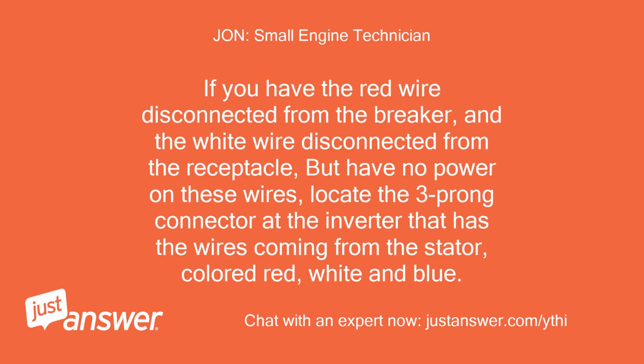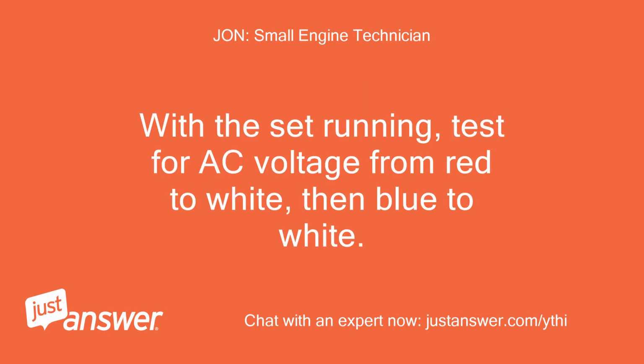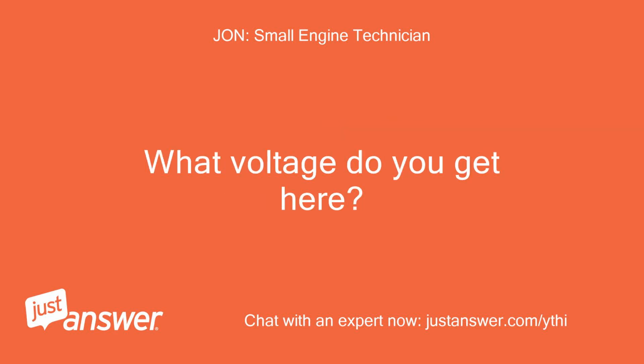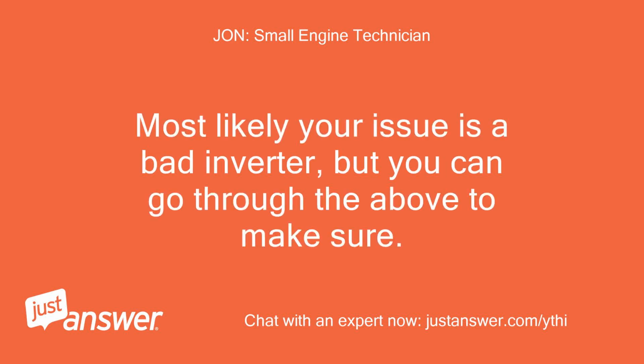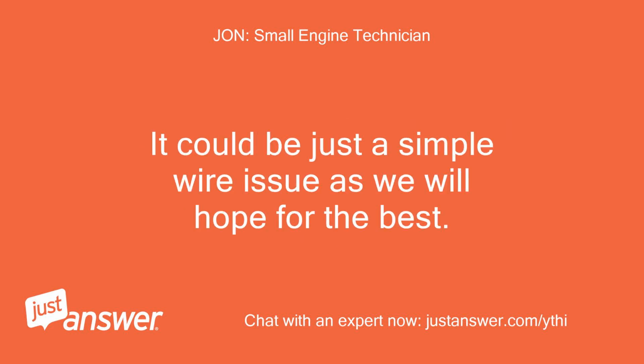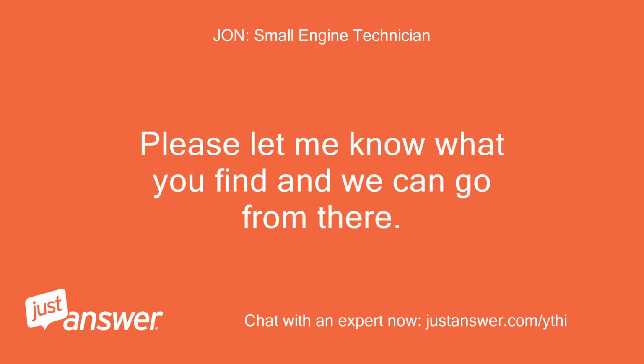If you have the red wire disconnected from the breaker and the white wire disconnected from the receptacle, but have no power on these wires, locate the 3-prong connector at the inverter that has the wires coming from the stator, colored red, white and blue. With the set running, test for AC voltage from red to white, then blue to white. What voltage do you get here? Most likely your issue is a bad inverter, but you can go through the above to make sure. It could be just a simple wire issue, as we will hope for the best. Please let me know what you find and we can go from there.